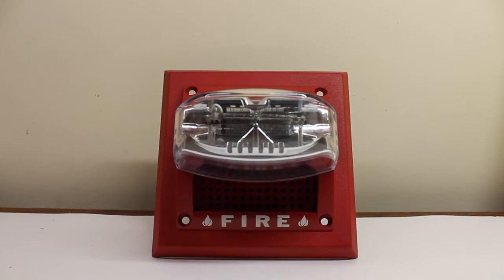Now let's go on to test the speaker itself. I have a 25 volt signal going in, so it's going to be on half watt. Without further ado, let's start off with a female Fire-Lite voice evac message: 'May I have your attention please? The signal you have just heard indicates a report of a fire in this building. Please proceed to the nearest exit and leave the building.